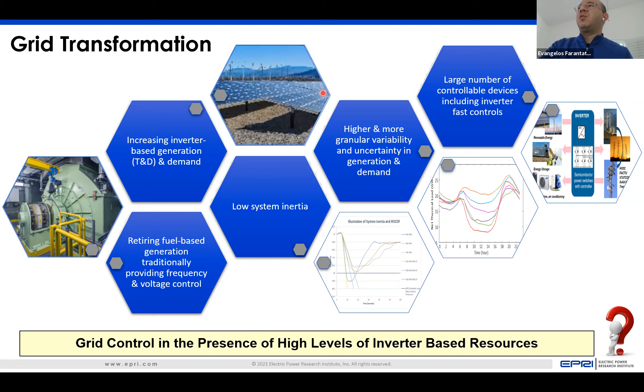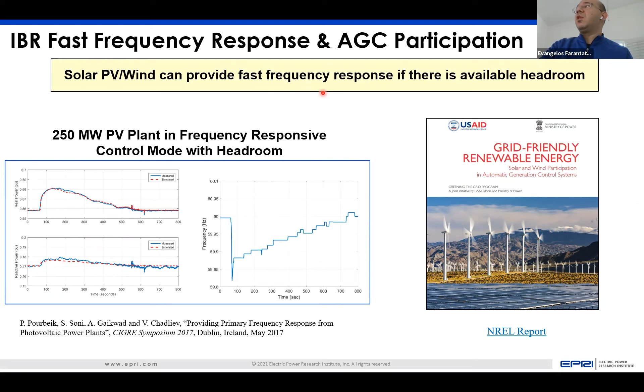And the answer is yes, if there is available headroom. So if they don't operate at maximum power tracking and there is some headroom, they can provide some frequency response. They can provide fast frequency response and also participate in the AGC, the automatic generation controller used for frequency control.